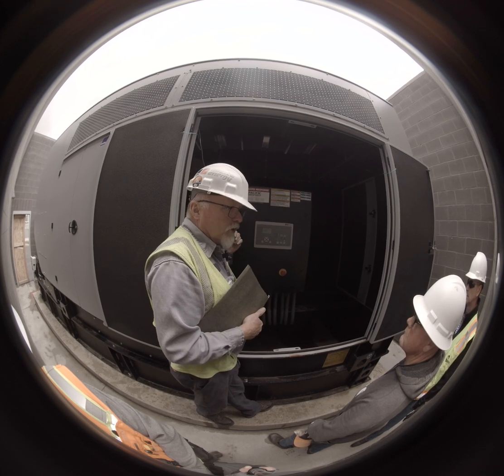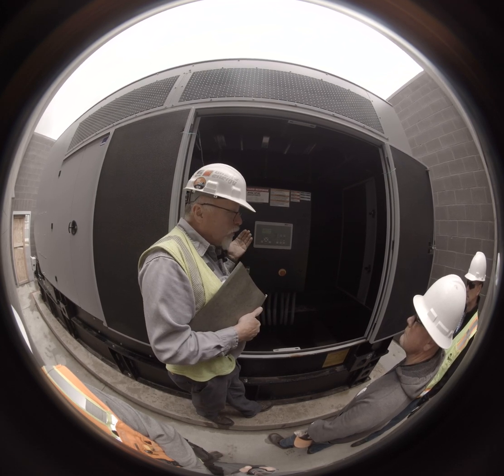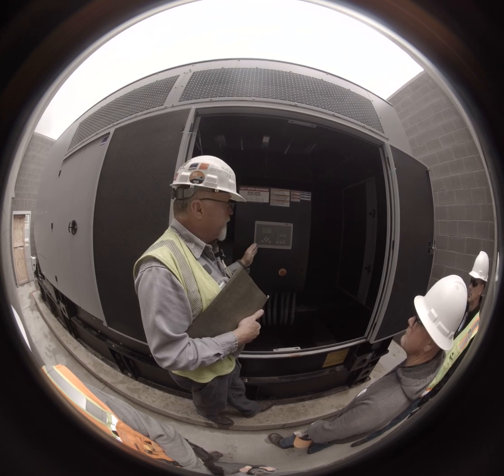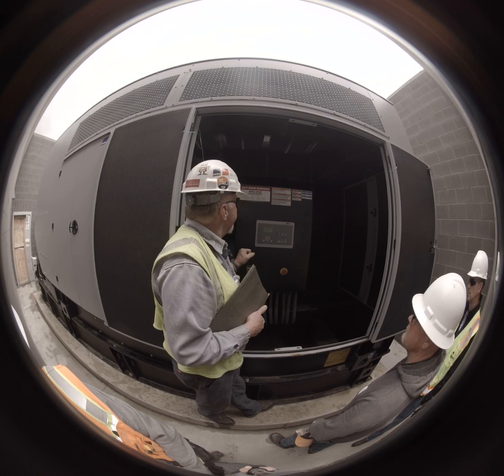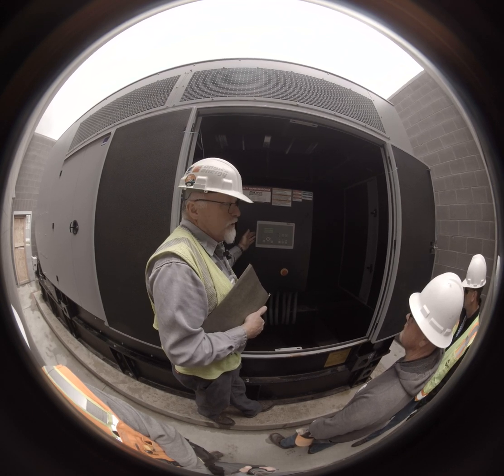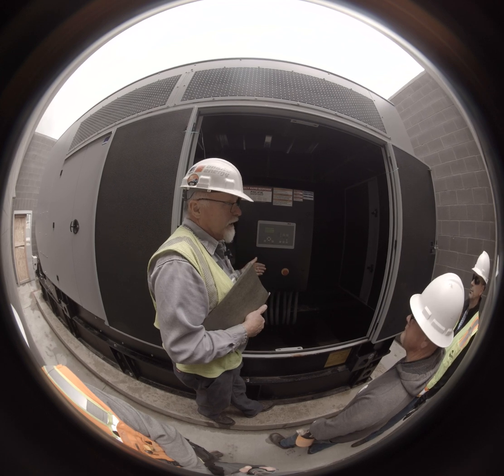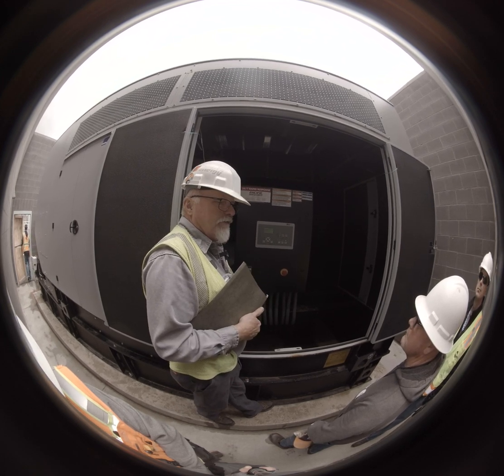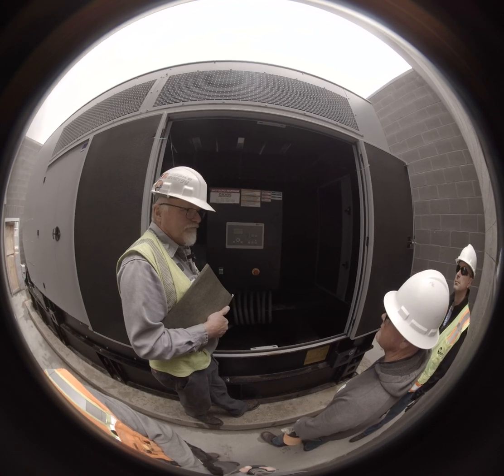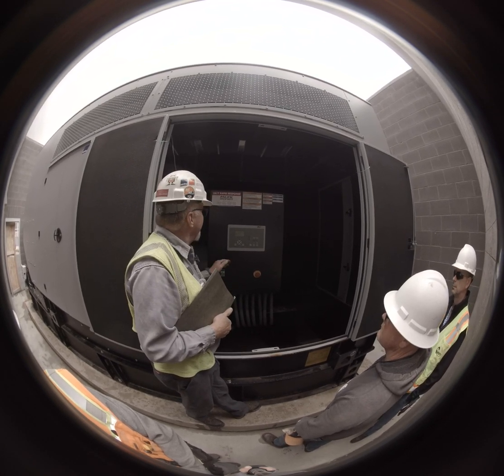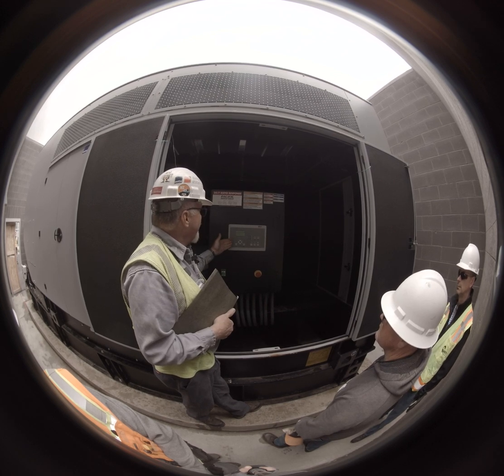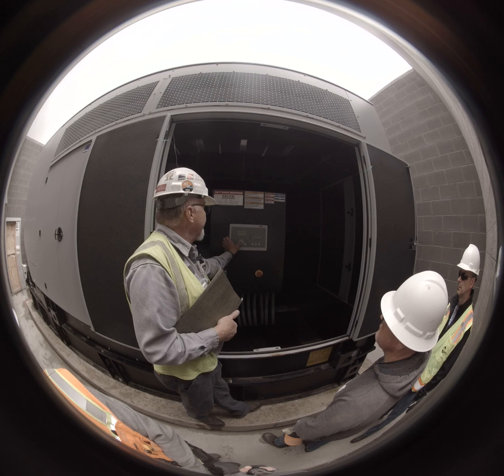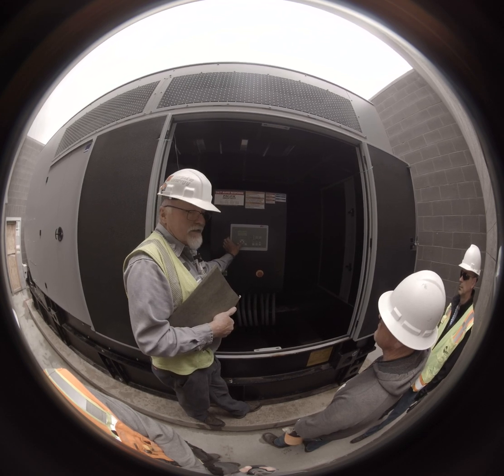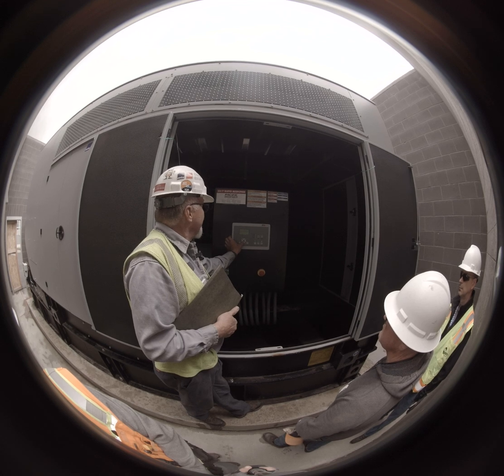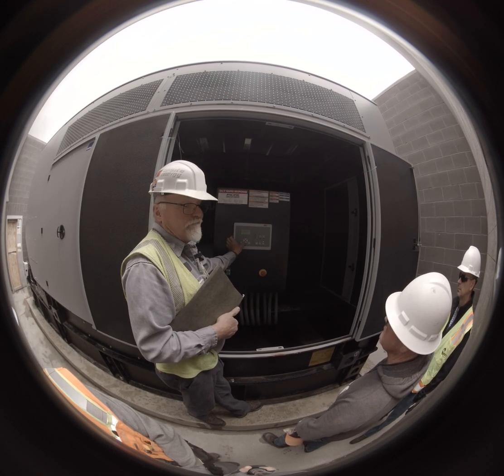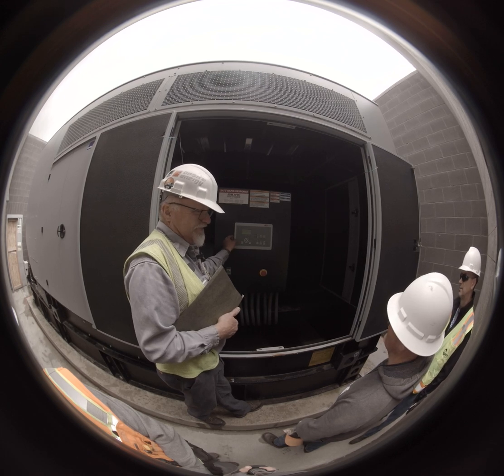Communications, you're not using Modbus 485 on this. You're only talking on the proprietary bus to the Annunciator. So communications really aren't going to do any good on that. Okay. System parameters, that one we definitely do not want to touch, because that's where I can tell it I want you to shut down at 165 degrees water temp, and it will. That's how I do my tests on it. Then you can set up your programmable inputs, programmable outputs, configure protection, all of that is within settings. You can change passwords. Please don't. No, I don't touch it.